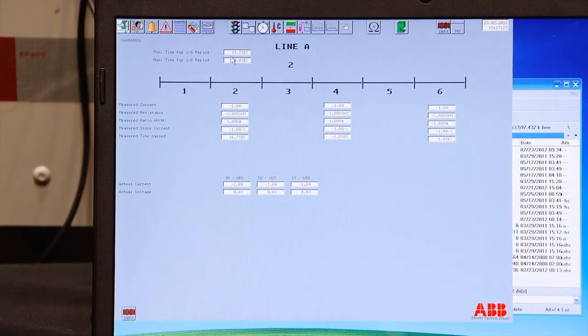You have the minimum time, 33.3 seconds. That's based on the frequency you have entered. Lower frequency means longer time, higher frequency shorter time. You have a maximum time. If he's not reaching saturation within this time, he will stop and tell you that the frequency is either too low or too high. So step number 2 is finished.